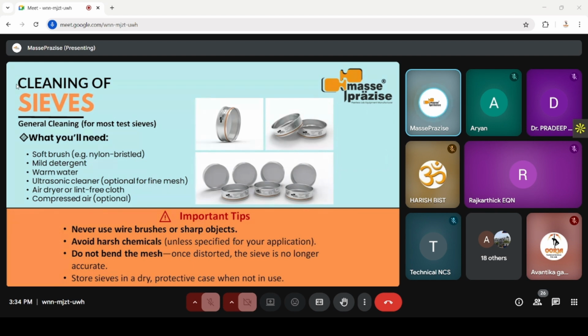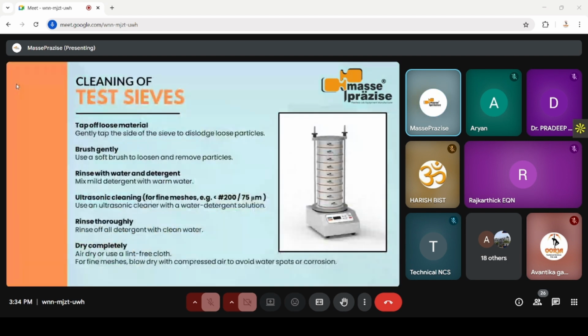In the first step, gently tap the side of the sieve to dislodge the loose particles. Do not bang it or tap against a hard surface. Tap the sieve very precisely. Tapping on hard surfaces can warp the mesh. Brush gently. Use a soft brush, either a nylon brush or a camel hair brush, to loosen and remove the particles from inside to outside. Brush from the bottom side to outside. So you have to use the brush from inside of the mesh, and then again you can use the tapping process to remove the particles that came out.